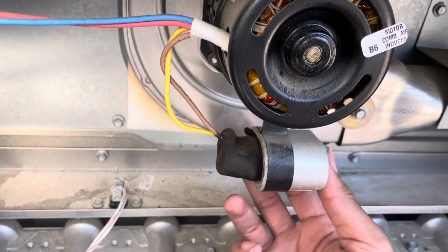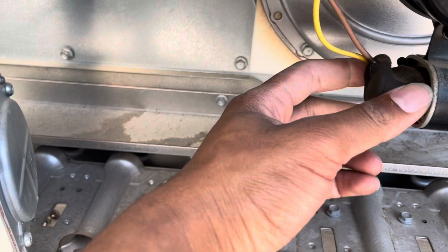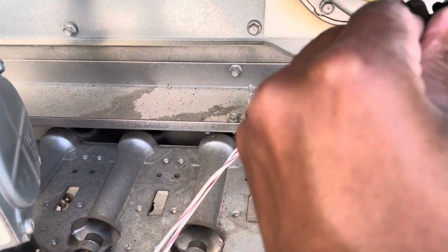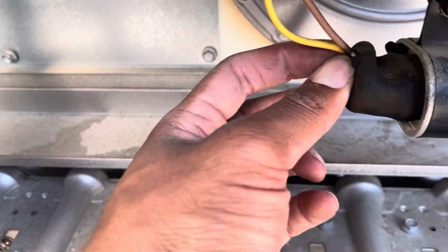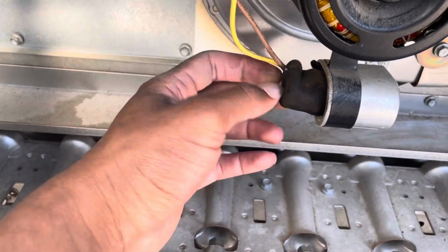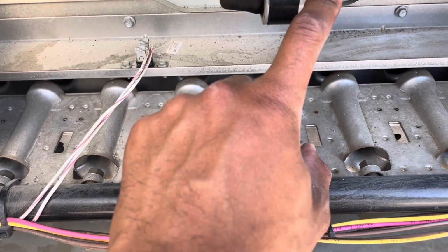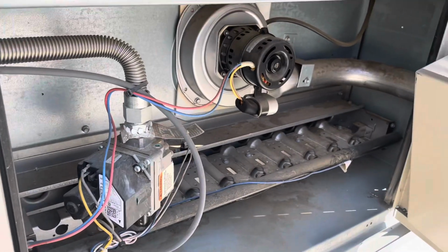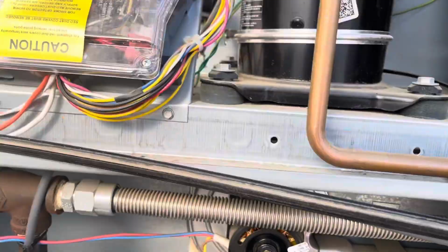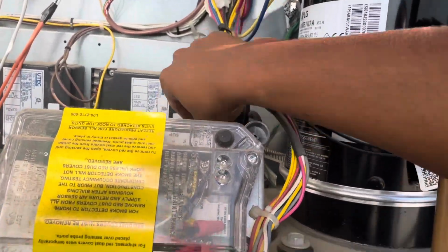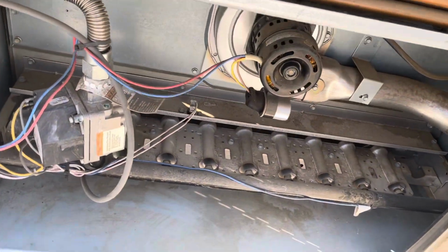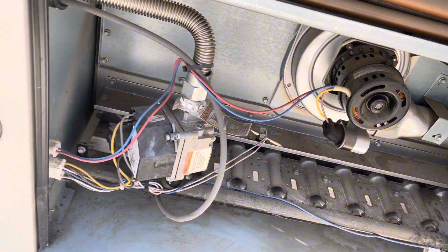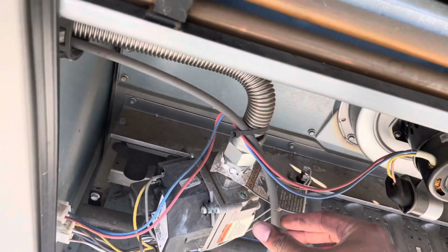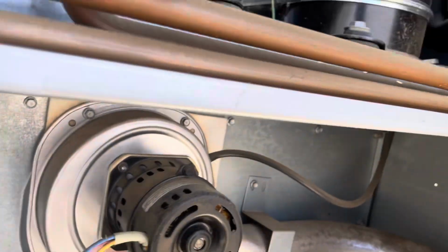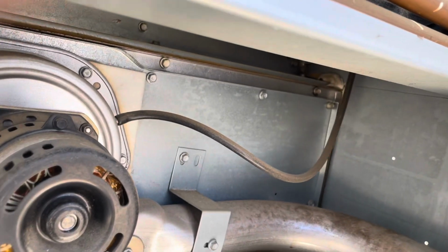But this capacitor doesn't look bloated or anything like that. Connections are tight. So yeah, you can check your capacitors, check your wire connections, check the pressure switch connections. Make sure your connections are good, tight, and nothing is corroded or anything like that. Check the condition of your hoses going to, right here, the condition of your hoses going to your pressure switches.